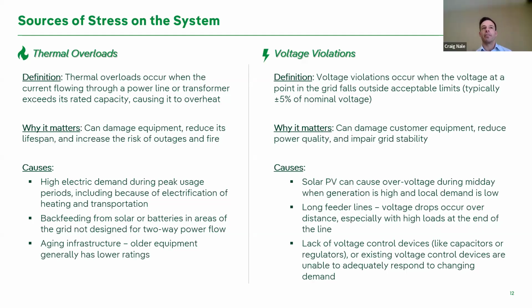So with thermal overloads, if we've got too much flowing over the system, it's going to cause the power line or the transformer to exceed its rated capacity, and it's going to overheat, causing damage to the equipment. This is due to common high electric usage, but it can also be attributed to backfeeding from solar or batteries sending power back into the grid.